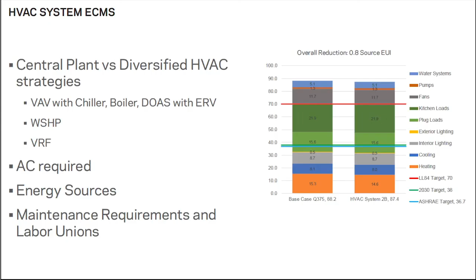On the next slide, we talk about the individual components related to the distribution, the piping of the HVAC systems. We had the benefit of, like I said, an already designed building. We were able to reduce airflow because of our reduced loads in the building. However, we decided to keep the ductwork at the same size as the original design and not reduce the ductwork and save on that first cost, mostly because oversizing ductwork had a really good EUI savings. We also increased the piping insulation for the distribution of chilled and hot water.